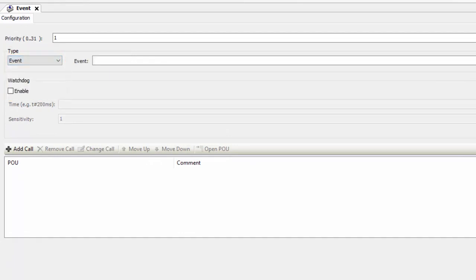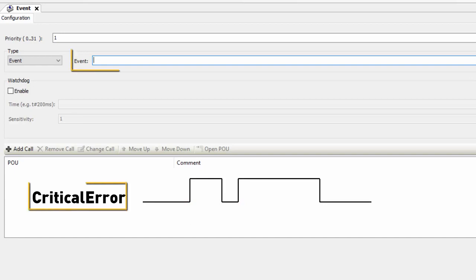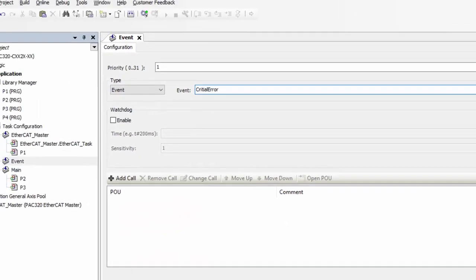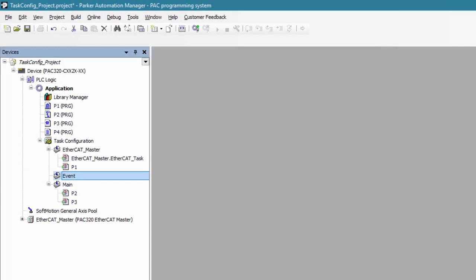This means that this task will only execute the logic of the programs assigned to it once. This task is triggered by a rising edge of a bool. So let's say in this example that we want this task to be triggered by a global variable called CriticalError. I simply just have to type it in here. I'll click my program called P4 and drag it under the Event task.